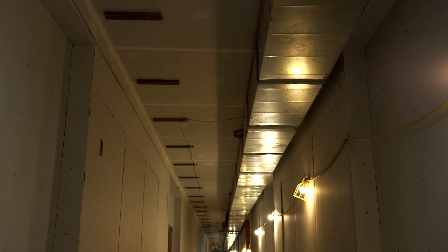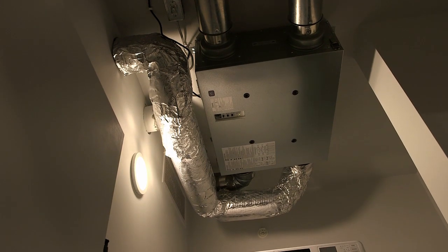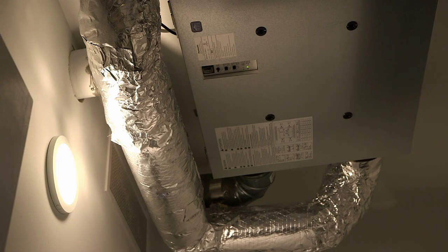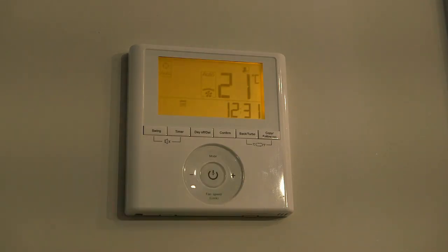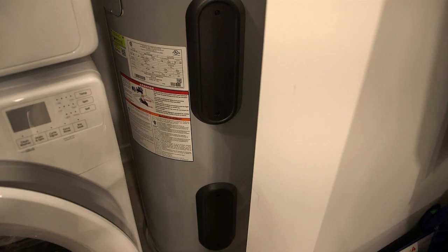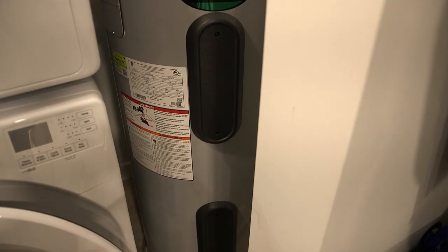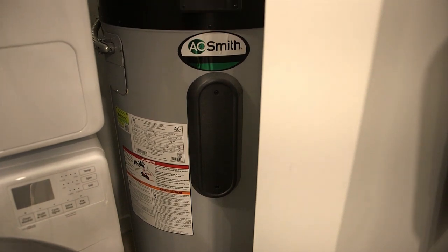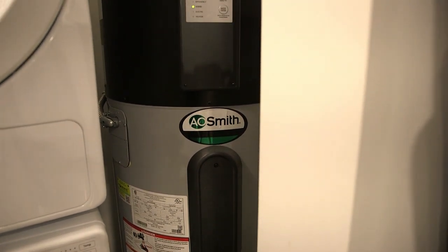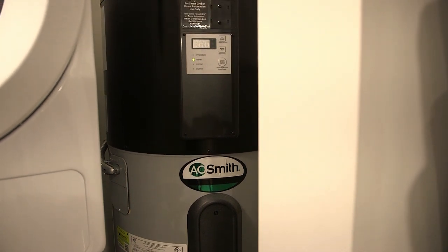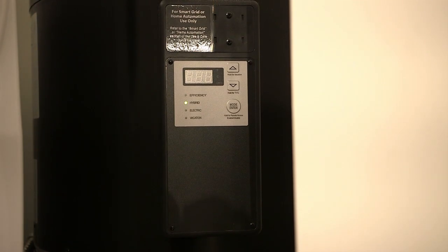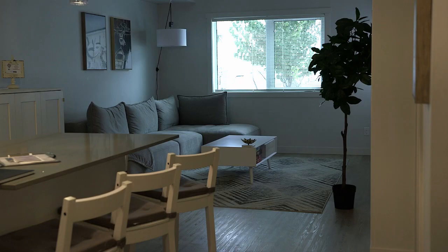Both buildings have centralized and decentralized HVAC systems. The common areas were ventilated through a central heat pump makeup air unit for heating and cooling, and the suites are ventilated through the individual decentralized ERVs coupled with individual fan coils for personal heating and cooling control. The domestic hot water is a decentralized system using 189-liter air source heat pump hot water heaters in each suite. The exhausted cool air from these water heaters also contributes to reducing cooling loads in the warmer months and can be switched from hybrid mode to fully electric during the cooler months to reduce heating demand.